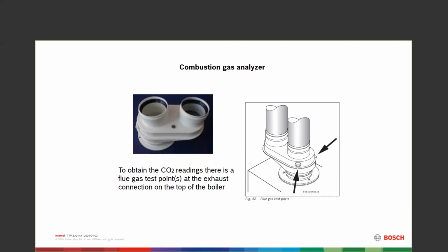They ought to be all the same. If your CO2 and your CO go up, then chances are you have a leak there somewhere, either in the boiler compartment or some other exhaust gas recirculation going on back into the venting. So that's the easiest way for me. Test it with the cover off, test it with the cover back on, and see how that goes for you. Like I said, they should be the same with no leaks, with everything properly installed.